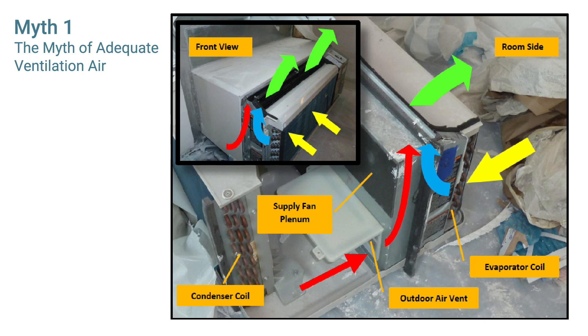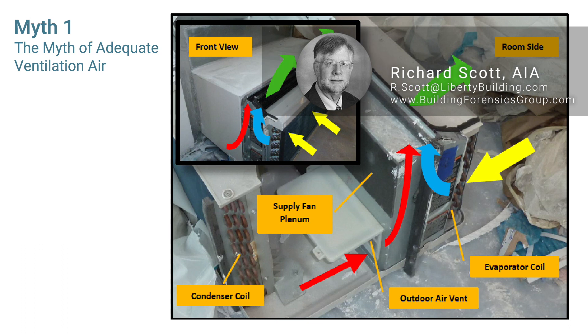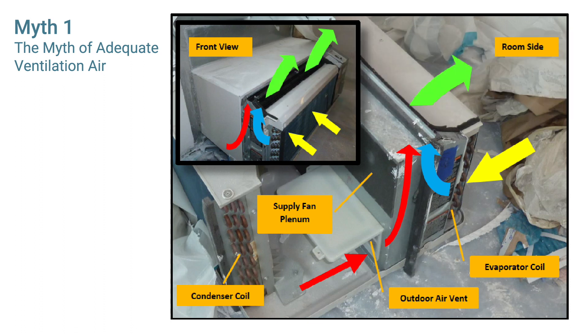In a hot humid climate, wouldn't keeping the door closed prevent outside air from coming in and avoid the humidity problem? Yes, that would be one way, but as discussed in this presentation, we expect the PTAC — in the absence of any other makeup air system — to provide both code-required ventilation and positive pressurization of the room. With the door closed, that won't happen. However, even with the door open, you won't get the ventilation and pressurization required to adequately keep a room from having mold problems.